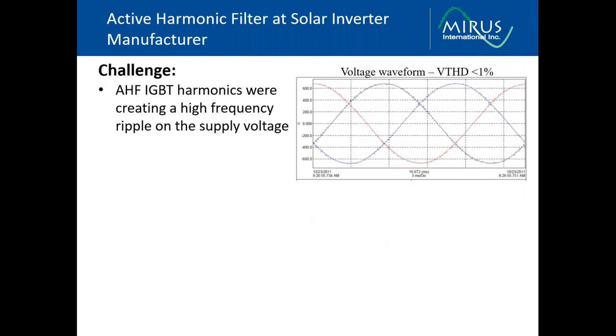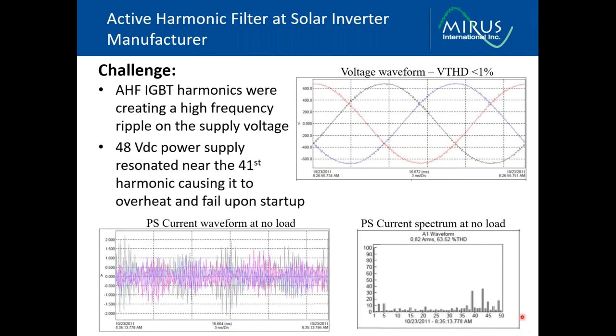When I went to the site, took some measurements, you can see the voltage waveforms to the right here on the screen. The voltage distortion was less than 1%, so by all accounts, extremely low voltage distortion, well within recommended standards for harmonic limits. However, this voltage had a very high frequency ripple, and when I investigated that further, I found out that it was in around the 39th to 43rd harmonic.